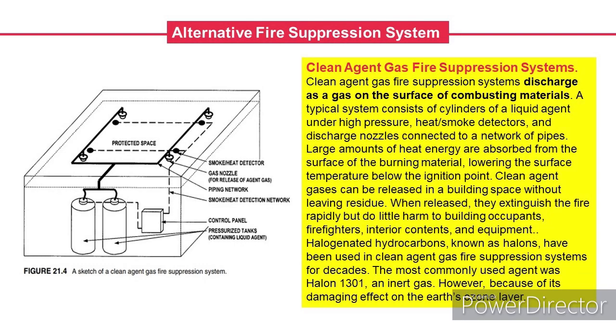Second is the clean agent gas fire suppression systems. Clean agent gas fire suppression systems discharge as a gas on the surface of combusting materials. A typical system consists of cylinders of a liquid agent under high pressure, heat/smoke detectors, and discharge nozzles connected to a network of pipes. Large amounts of heat energy are absorbed from the surface of the burning material, lowering the surface temperature below the ignition point. Clean agent gases can be released in a building space without leaving residue. When released, they extinguish the fire rapidly but do little harm to building occupants, firefighters, interior contents, and equipment. Halogenated hydrocarbons, known as halons, have been used in clean agent gas fire suppression systems for decades. The most commonly used agent was halon 1301, an inert gas. However, because of its damaging effect on the Earth's ozone layer.